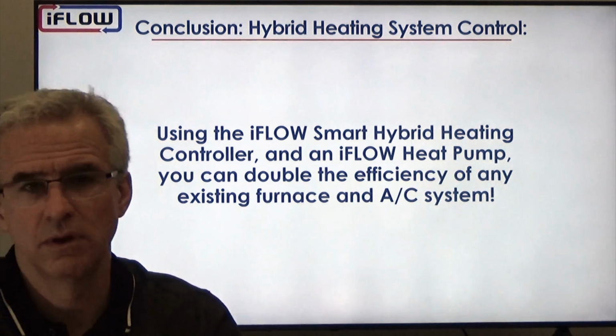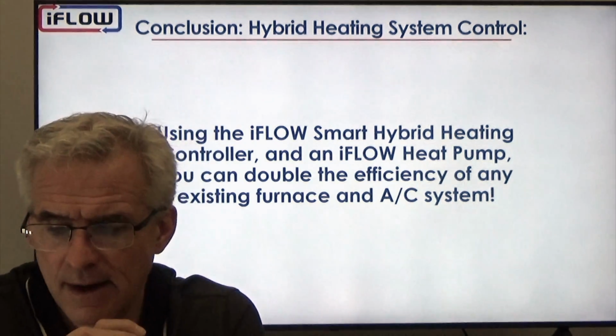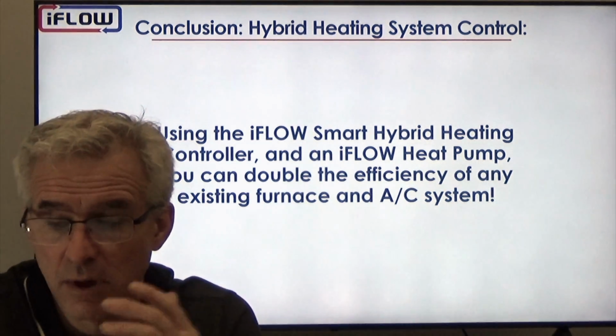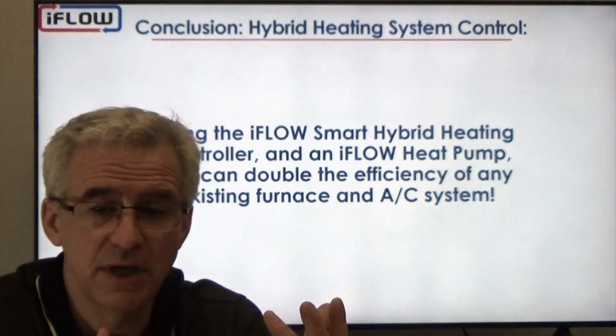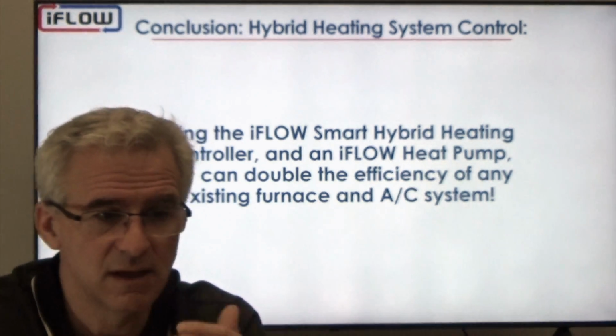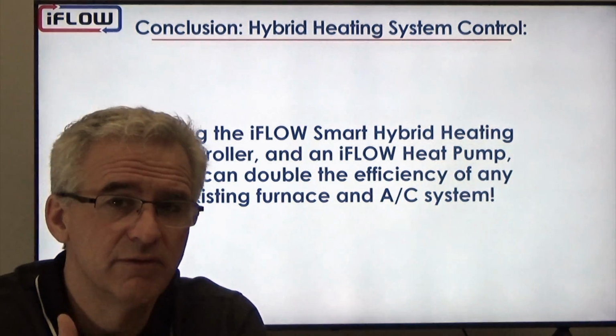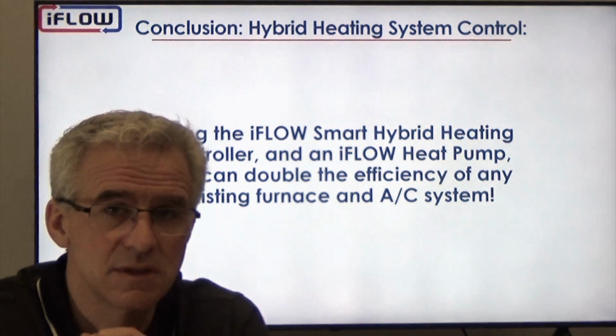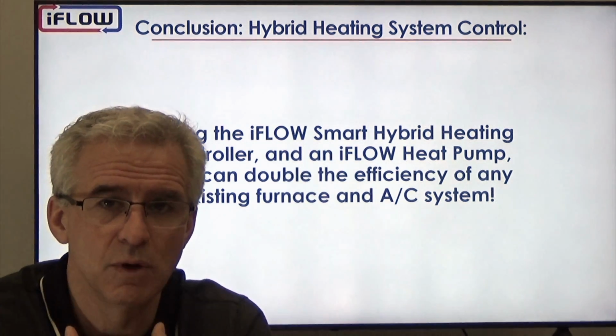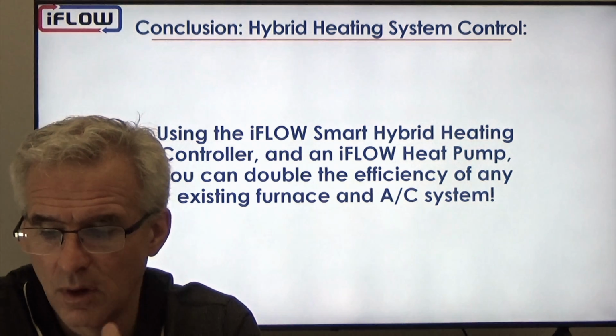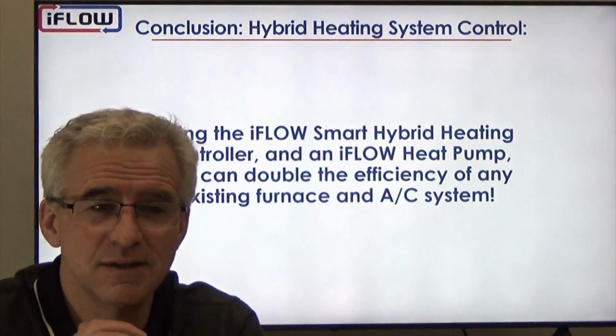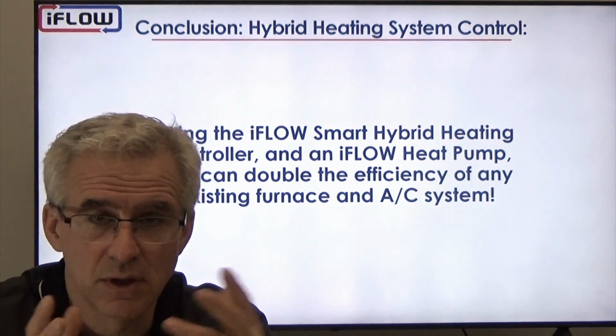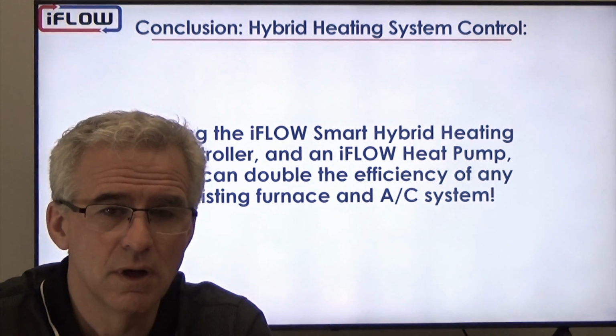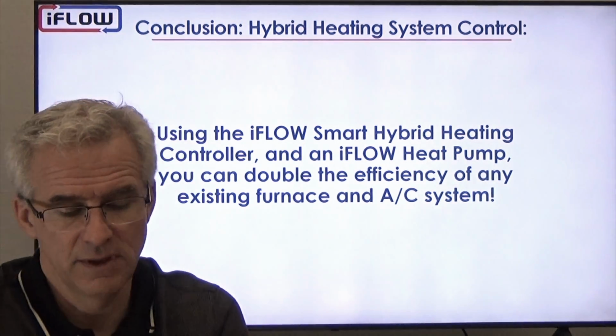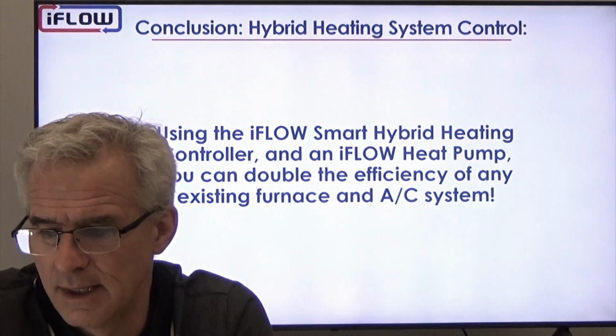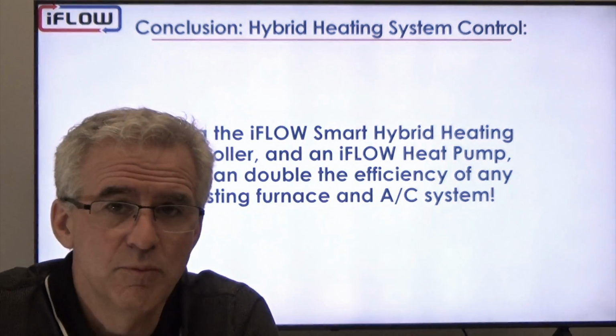So to conclude, we're looking at our hybrid heating controller. So if you're using the iFLOW smart hybrid heating controller and let's say the iFLOW heat pump and you've replaced your old AC and you have your existing furnace, then we can effectively double the efficiency of your system by combining the heat pump using our smart controller. We will show you how we get those savings in another video, but all to say, yes, we double the efficiency and we reduce your carbon footprint by half. So definitely some advantages to using our hybrid system, using our heat pump with our smart controller.